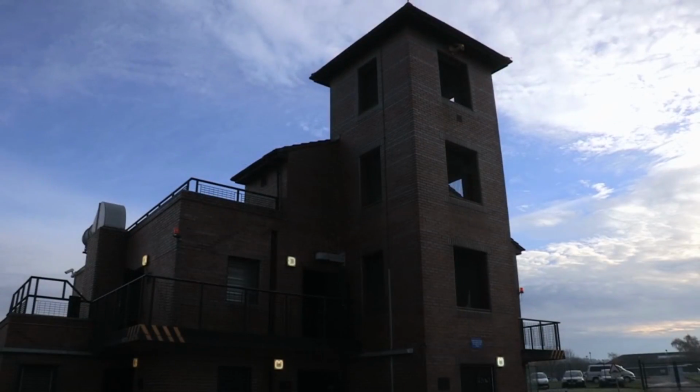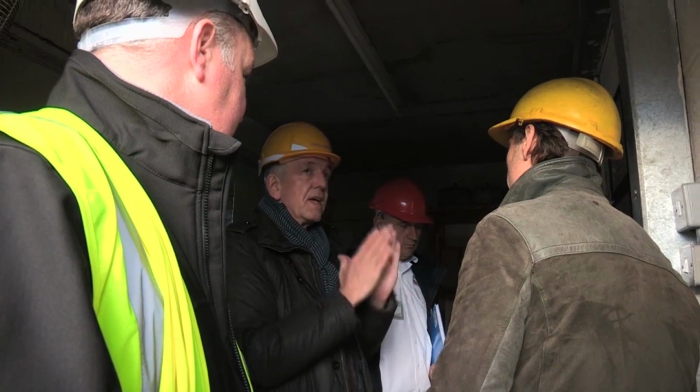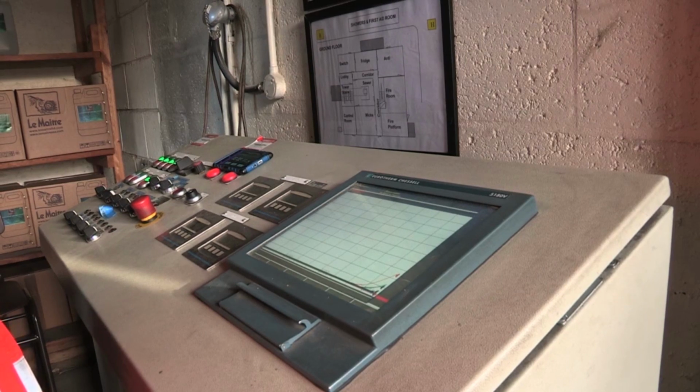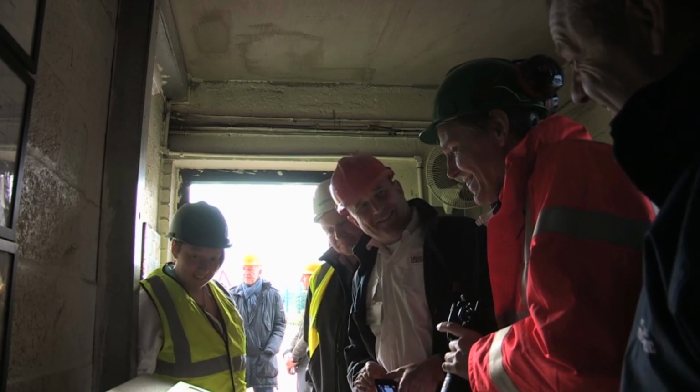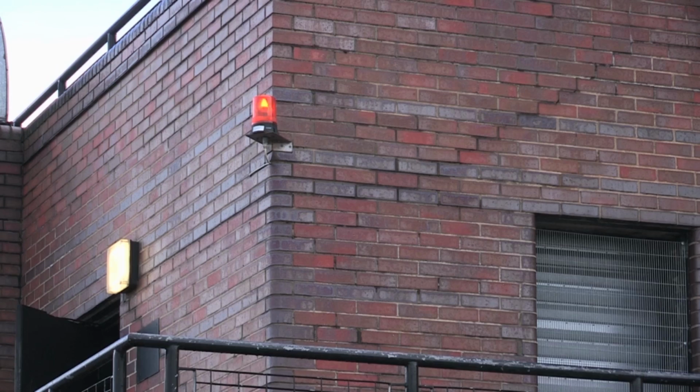It has stories above it and a control room where you can see electronic readings of the temperatures caused by the fire. We had a couple of sensors in the room, one relatively close to the fire and one further away. We plotted this and videoed the readout from the control panel, and we could actually see the temperature rises all around the building. What we did is kept the door to the stairs open, which fully ventilated the room.